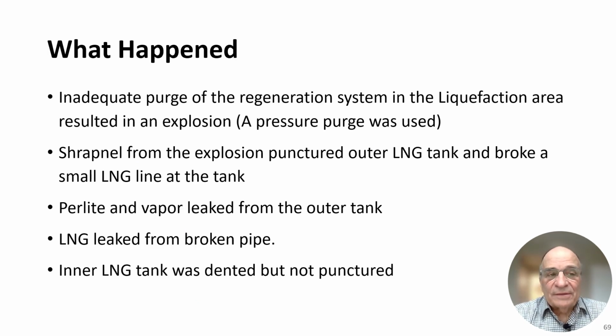Here's what happened. Inadequate purge of the regeneration system in the liquefaction area resulted in an explosion. A pressure purge was used. Shrapnel from the explosion punctured the outer tank of the LNG tank and broke a small line at the tank. Perlite and vapor leaked from the outer tank. LNG leaked from the broken pipe. The inner tank was dented but not punctured.